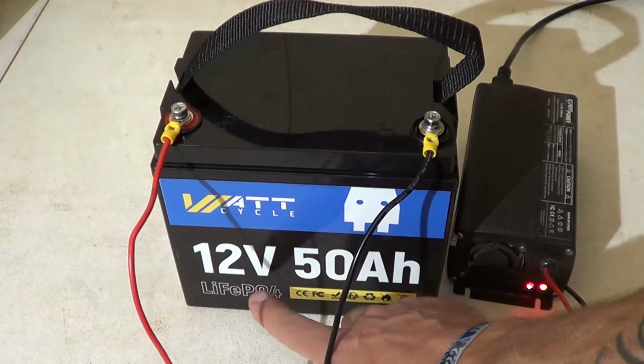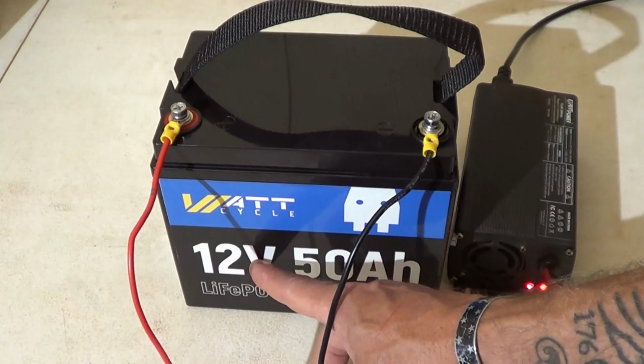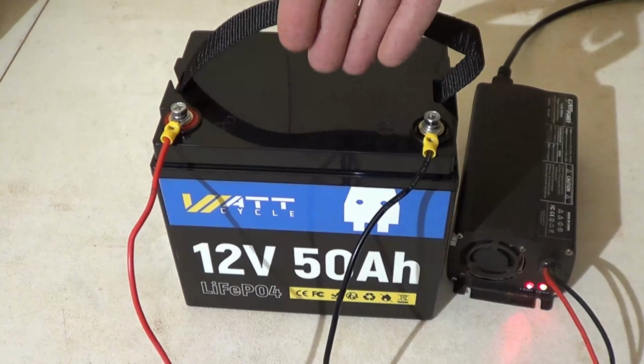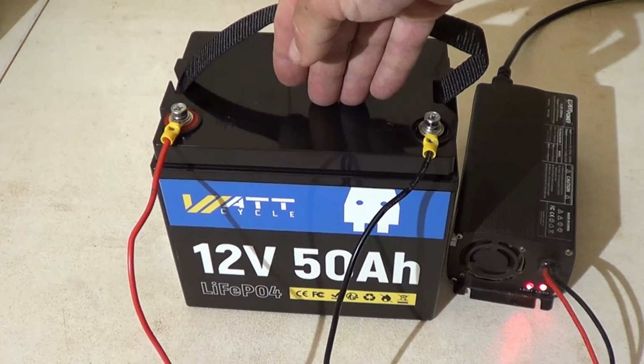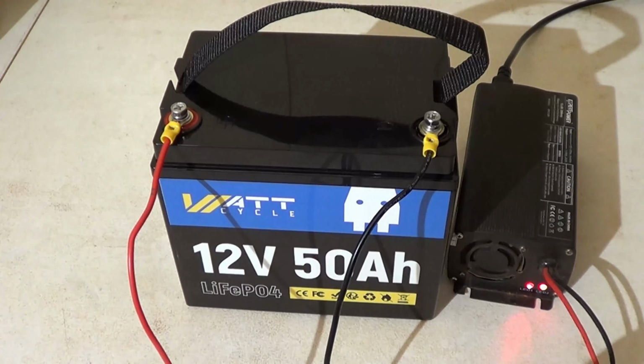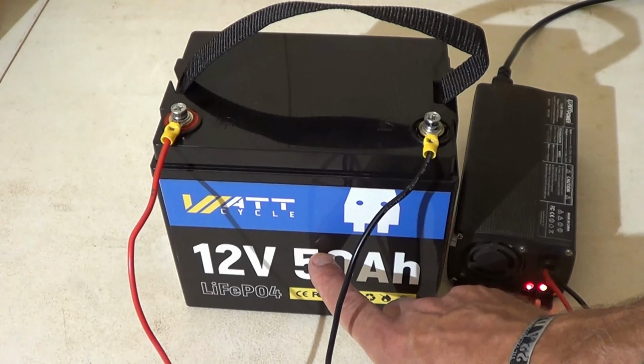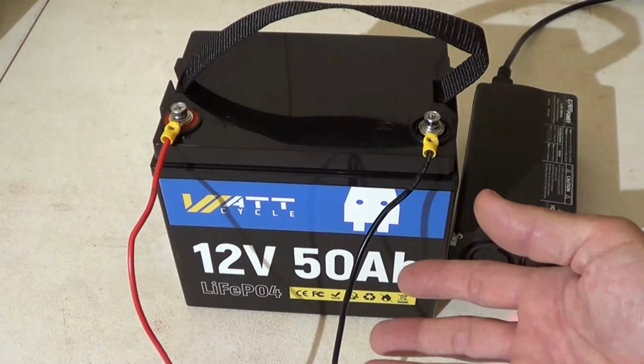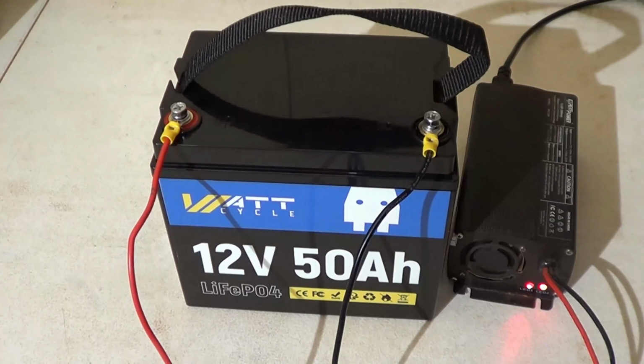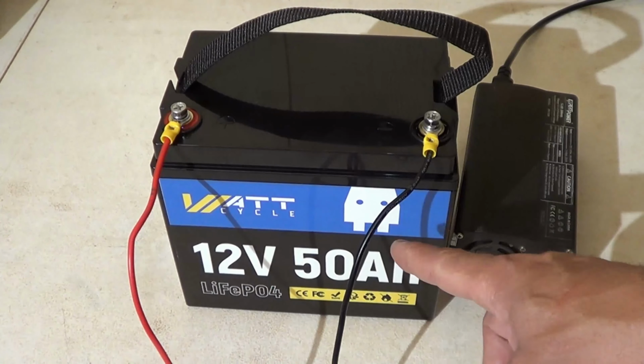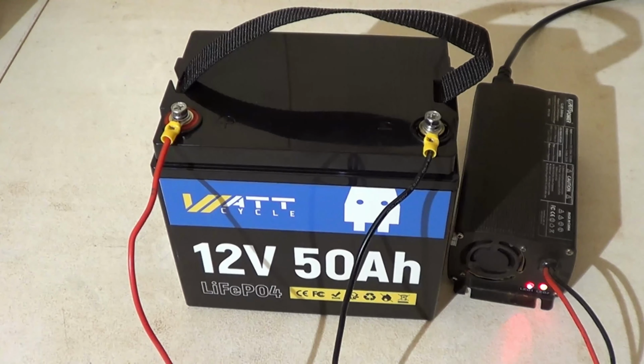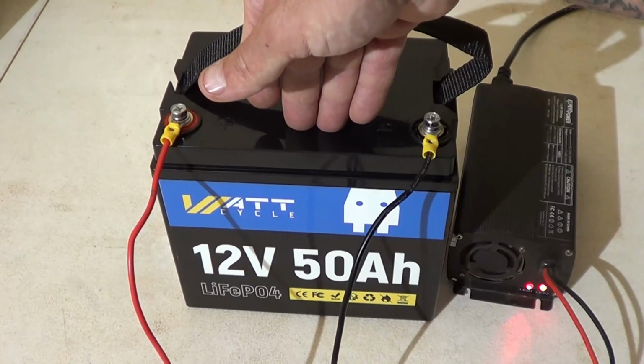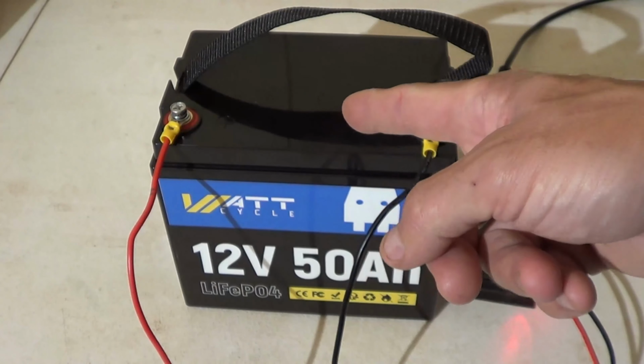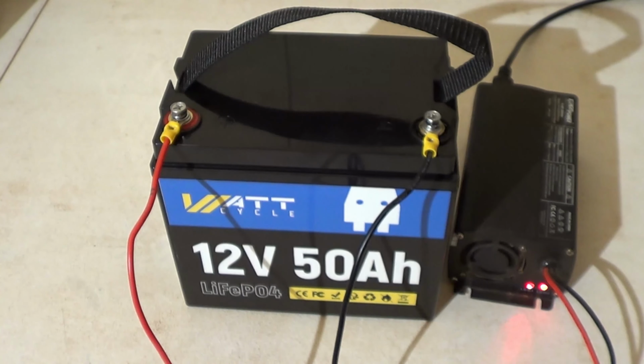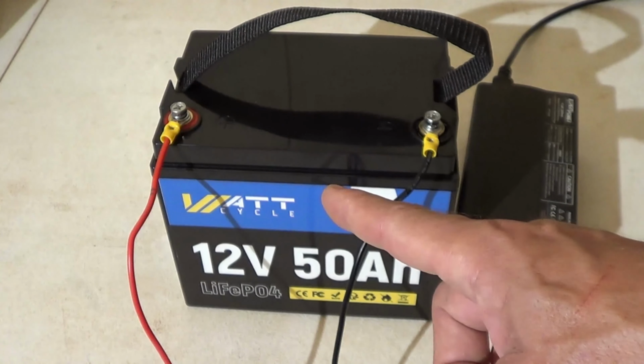The rated voltage of this battery, as you can see here, says 12 volt, but it's actually 12.8 volt. Your standard charging voltage for this battery is 14.6 volts. The shipping voltage, as we saw, was somewhere between 12.8 volts and 13.5 volts. We saw earlier that we were around 13.3 volts, so that battery ships at about half capacity. This battery has a 6,000 cycle rating at 80% depth of discharge. That is fantastic. This battery is IPX7 dust and waterproof. So that's fantastic. Your storage temperature for this battery is anywhere from 32 degrees all the way up to 140 degrees Fahrenheit.